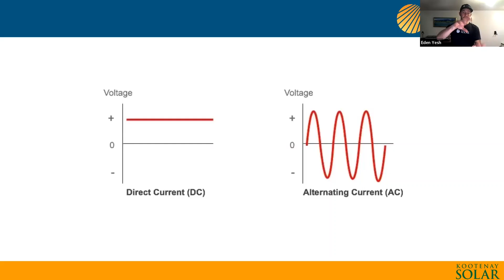Again, direct current coming off the panels, you have to invert that to alternating current. And you do this with inverters. There's several types of inverters. The industry for the first 30 or 40 years used string inverters. But if one panel got shaded, because they were all on one string, you would be as strong as the weakest link. So if an eagle craps on one panel, a big crap, your entire panels are gone, right? You're now down to 50% production because it's called soiling, right? If there's leaves over top of one panel, all of your other panels are now at 50% production.